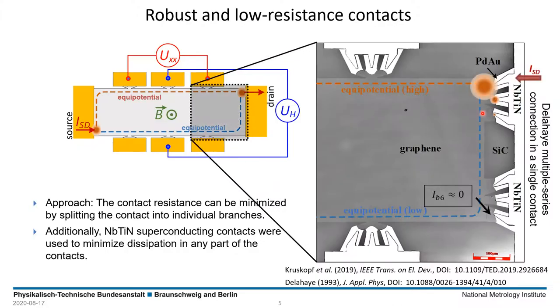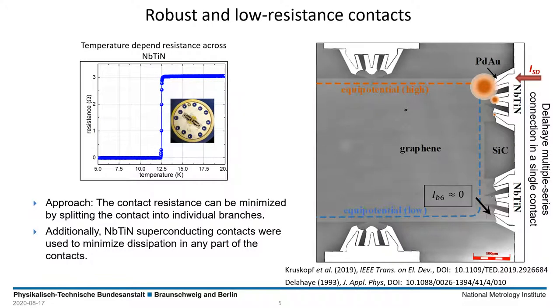The quantum Hall devices apply a reworked contact design on which I was working at NIST. It uses source, drain, and Hall contacts that are split into individual branches to integrate the principle of the so-called Delahaye multiple series connection. Additionally, the contacts apply a layer of superconducting niobium titanium nitride to minimize dissipation.